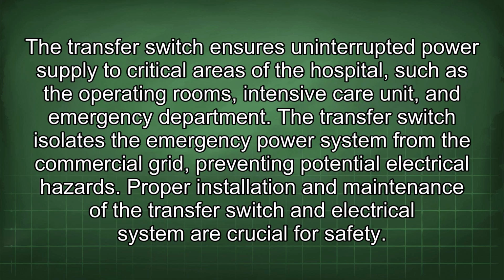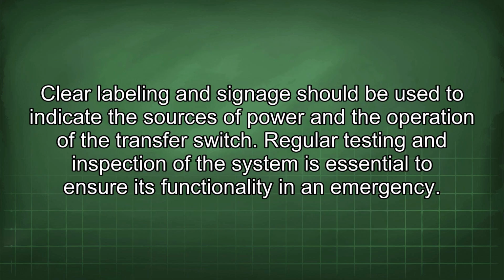The transfer switch ensures uninterrupted power supply to critical areas of the hospital, such as the operating rooms, intensive care unit, and emergency department. The transfer switch isolates the emergency power system from the commercial grid, preventing potential electrical hazards. Proper installation and maintenance of the transfer switch and electrical system are crucial for safety. Clear labeling and signage should be used to indicate the sources of power and the operation of the transfer switch. Regular testing and inspection of the system is essential to ensure its functionality in an emergency.